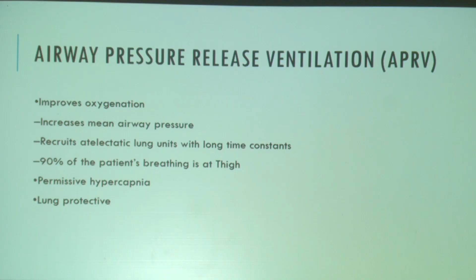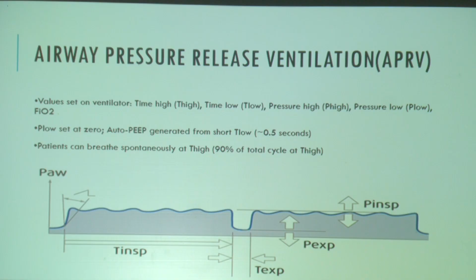Another graphic showing on a different ventilator how the patient should look with their pressure time waveforms. We have our inspiratory time, which is very long, our very short expiratory time, and then another long inspiratory time. And the patient, you can see, is taking little breaths on top of that time high to get rid of some of the CO2. You'll notice during the exhalation, it's not returning down to baseline, and so we are generating auto PEEP, like we talked about previously.